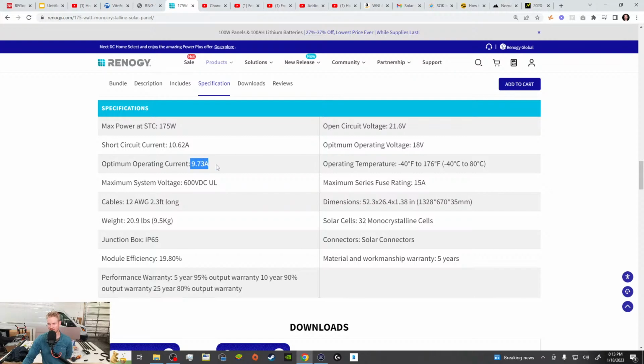This is what we can expect out of the solar panel, and we're going to use that to size the system. In our case, we've got 9.73. We know we're probably not going to get there efficiency-wise, so the good news is it's very rare that it would ever go higher than that. So you do 9.73 times 2, because we've got 2 of the 175 watt solar panels, and that gives us about 19.46 amps.